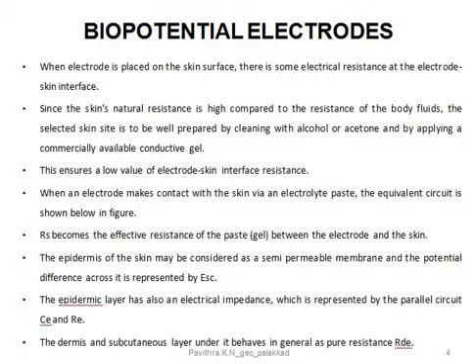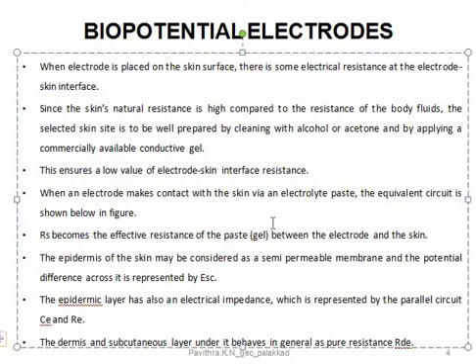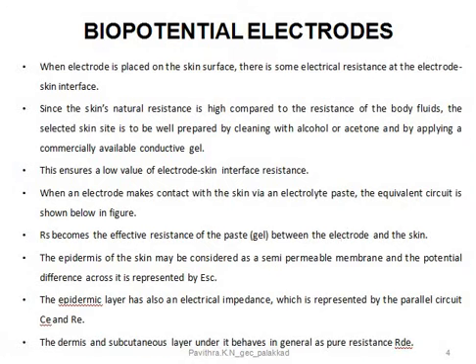The chemical reaction that occurs between the metal and electrolytes influences the performance of biopotential electrodes. When the electrode is placed on the skin surface, there is some electrical resistance at the electrode-skin interface. Since the skin's natural resistance is very high compared to the resistance of body fluid, the selected skin site must be well prepared by cleaning with alcohol or acetone before placing the electrode.